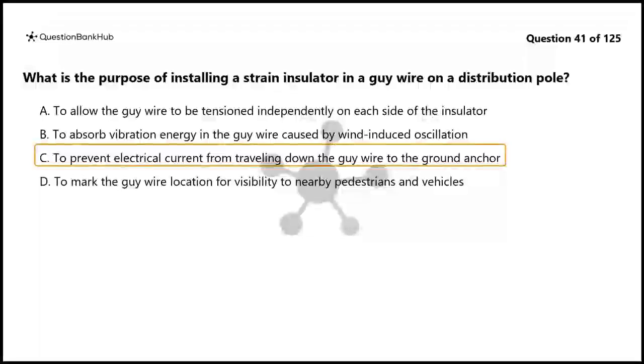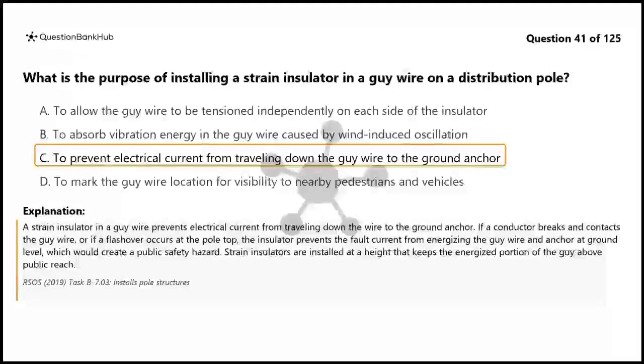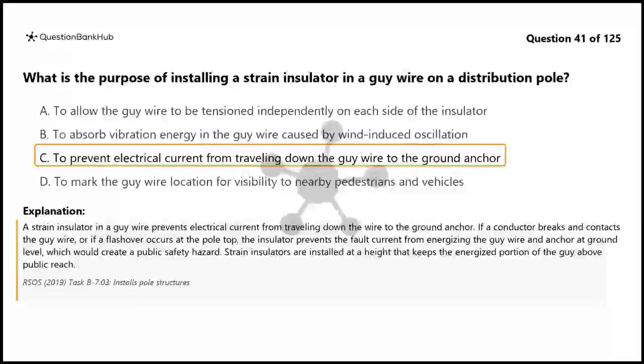The correct answer is C. A strain insulator in a guy wire prevents electrical current from traveling down the wire to the ground anchor. If a conductor breaks and contacts the guy wire, or if a flashover occurs at the pole top, the insulator prevents the fault current from energizing the guy wire and anchor at ground level, which would create a public safety hazard. Strain insulators are installed at a height that keeps the energized portion of the guy above public reach.